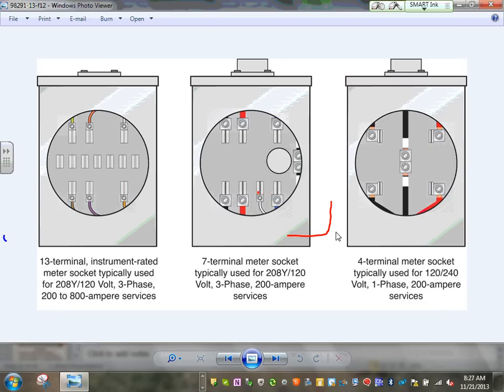The jaws that they have for the meters. If your voltage is 208, here's what you have: 208, 120. This is how it looks: phase A, phase B, phase C, and the neutral, of course, with them. If your system is 208, 120 up to 200 amp, you have all the phases here plus the neutral. So different configuration for different meters. That's what you have in your house. 120, 208. So when you buy a meter, 200 amp, 3-phase, it will look something like this. If it's 200 amp, 120, 240, it will look something like this. How many jaws they have? They call these jaws, meaning how many phases you want to break. So that's a typical application, guys, for your system in terms of the transformers.